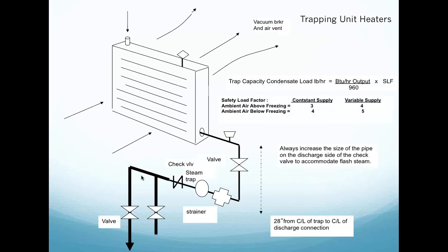Trapping a unit heater. A unit heater is nothing more than a steam coil with a fan built into it. So one of the reasons I wanted to show this to you is that with the temperature starting to cool off, we're going to have unit heaters coming on. We'll have steam traps below. And I wanted you to notice a couple different things. On this unit heater, I wanted you to see I've got a vacuum breaker at the top of this. I've got an air vent at the top of this unit heater.